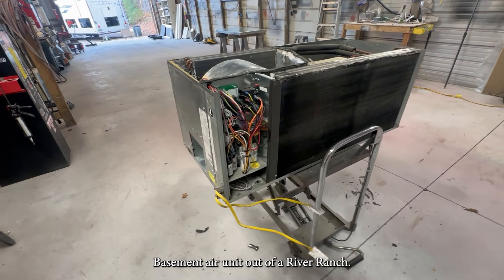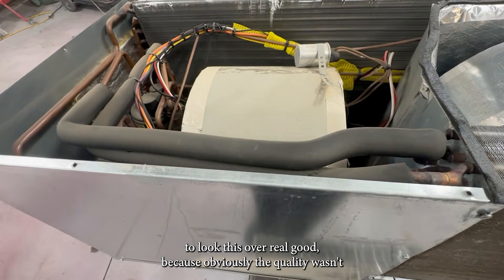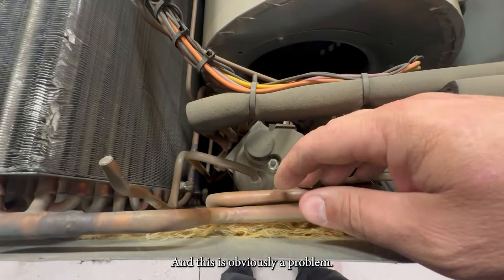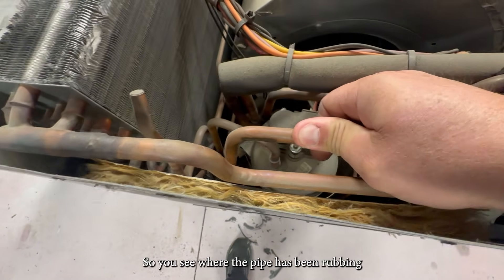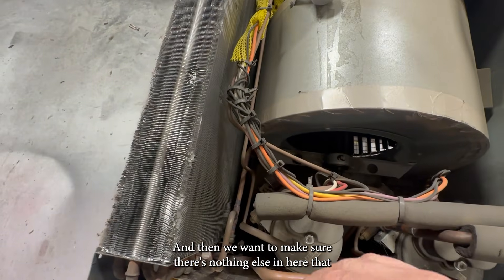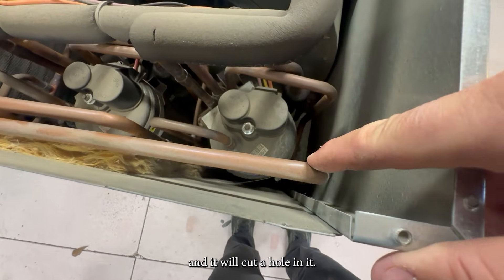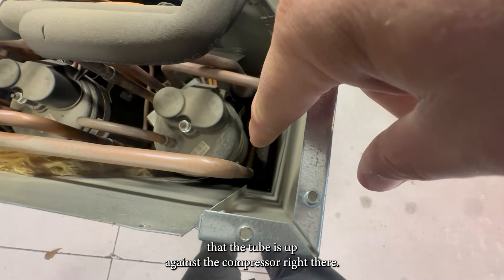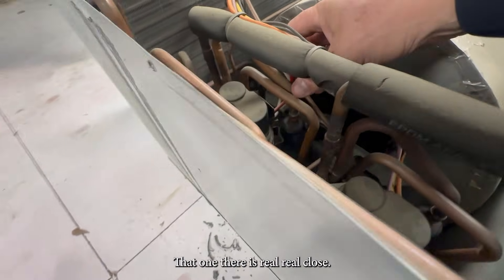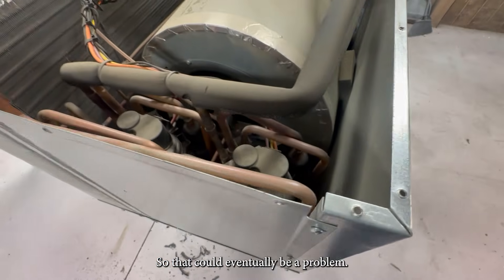Basement air unit out of a River Ranch — this is a Marvair unit. Mr. Lewis has got all the stuff off of here, so we always like to look these over real good because unfortunately the quality wasn't the best. And this is obviously a problem — you can see where the pipe has been rubbing. It doesn't look like it's done any damage, but it obviously has been rubbing. We want to make sure there's nothing else in here that could potentially be an issue — a lot of times this pipe is up against here and it'll cut a hole in it. You can see the tube is up against the compressor right there. So we're going to have to resolve that. I always look these over real good — that one is real close, so we're going to pull that apart a little bit. That one there is the same way, so that could eventually be a problem.